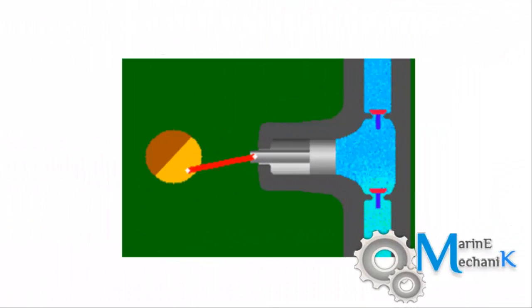As we discussed earlier, here is the simple animation for the reciprocating type of bilge pump. As you can see, the suction valve and the delivery valve lifts based on the piston movement from TDC to BDC. The piston rod is driven by the connecting rod, crosshead, and the crankshaft via the electric motor which drives through a gear or the pulley mechanism. In this animation there is no spring shown on the delivery and suction valve, and there is no air vessel also provided over here.